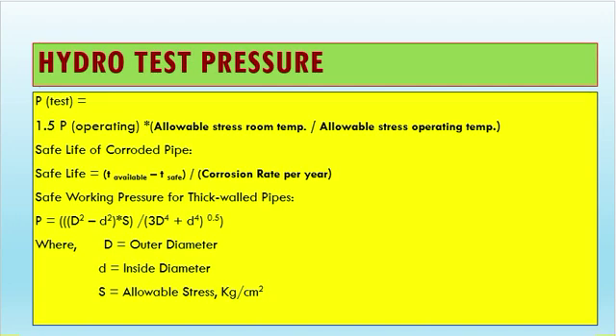For hydrotest pressure, the formula is: P = 1.5 × P_operating × (allowable stress at room temperature / allowable stress at operating temperature).